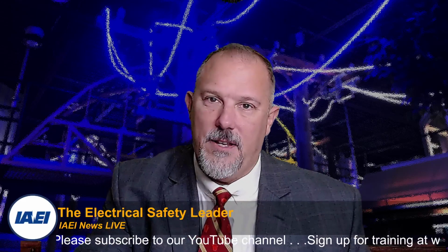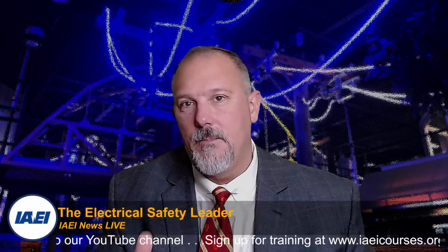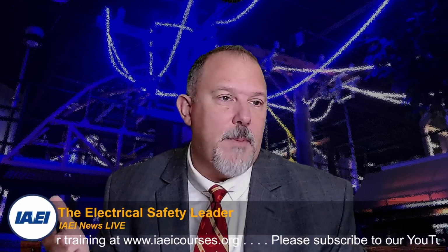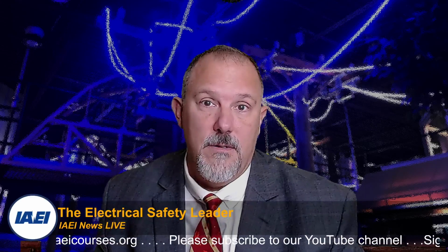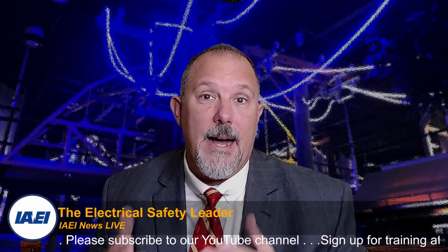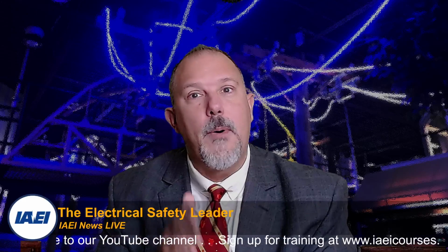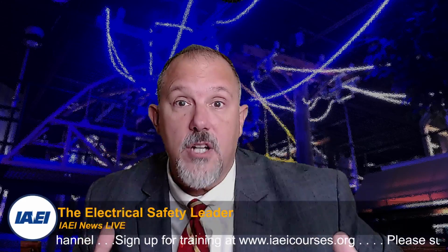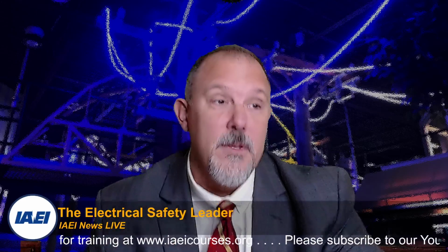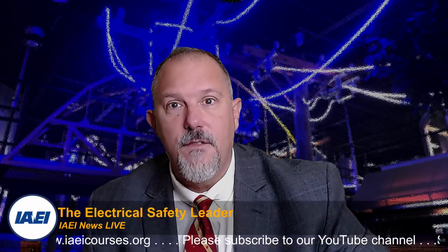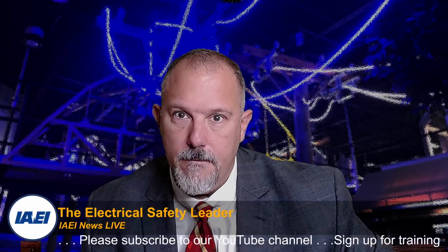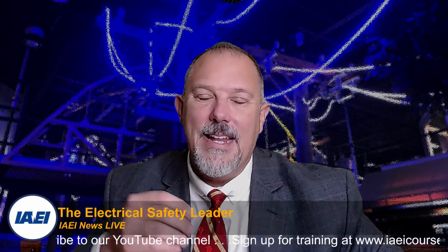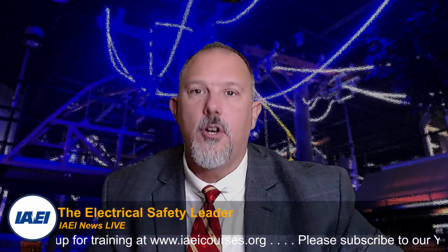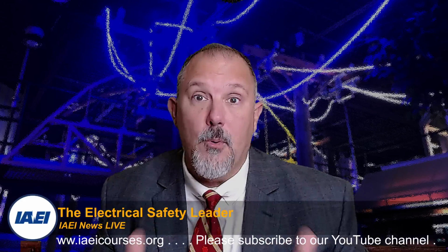Now I could plug in enough loads that I'm exceeding 20 amps, but I'm not at hundreds of amps or thousands of amps. I'm exceeding 20 amps by maybe another 5 or 6 amps, or maybe 10 amps, depending upon what I'm plugging in. I am experiencing an overload. And depending upon the time current characteristic curve, which is another great topic for an IAEI News Live for another day, the time current characteristic curve for the circuit breaker protecting my 20 amp circuit is going to determine how much time it lets that overload exist. And it could be that I turn all of that on, cut my wood, turn it all off, and I never trip the breaker. That's a temporary overload.